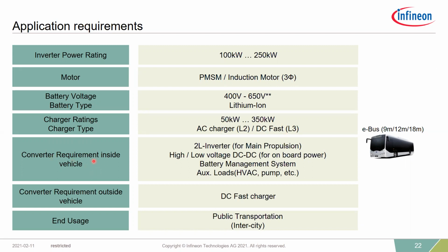Now, what kind of converter is needed for this electric bus application? Generally for the main propulsion, we need a two-level inverter because this is good enough. The motor has certain operational limits, which I'll go through in upcoming slides, but generally you cannot switch it beyond 10 kilohertz. The sweet spot could be less than 4 kilohertz, where you can operate at this 100 to 250 kilowatt power level. That's why today's 1200 volt silicon chipsets are good enough, or optimized, to handle this in a two-level topology.